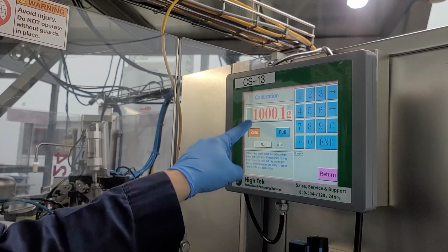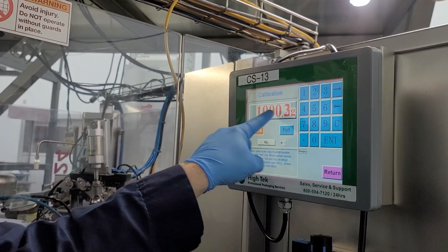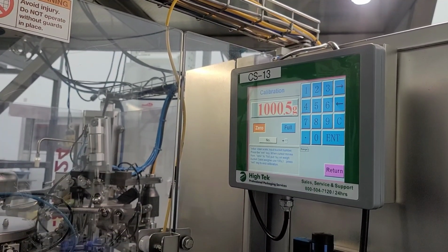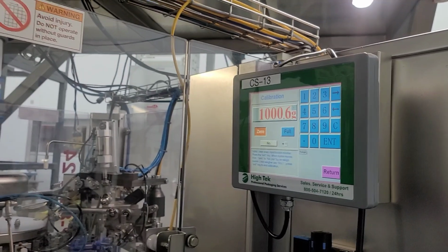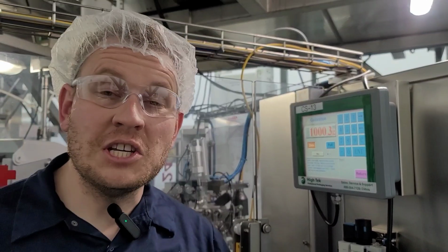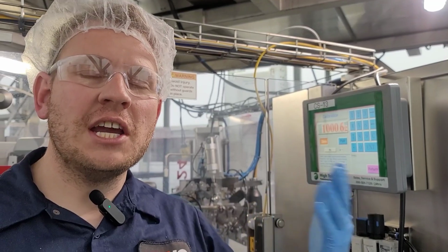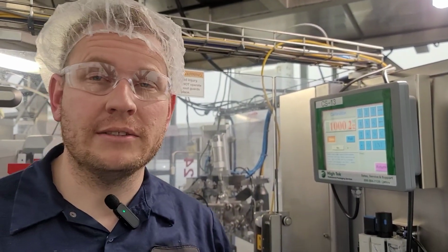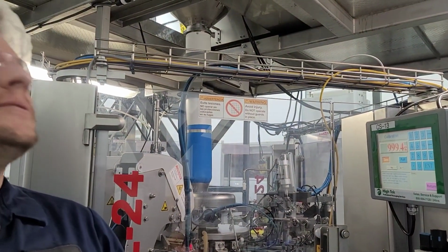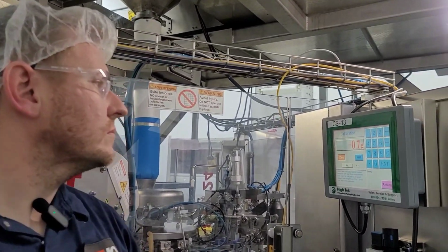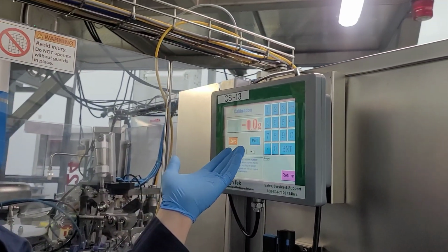The cursor moves back, and now you can read the 1 kilogram weight is now present on the load cell. At this point, tell the technician above to remove the weight. Okay, remove the weight. As you can see, the weight has now returned to near 0.